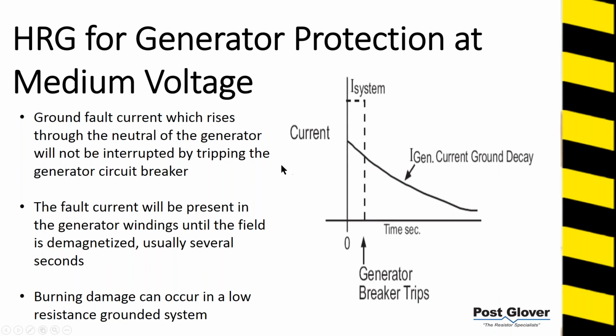And so once again, if you talk about hybrid grounding, that's the situation where you can't use high resistance ground exclusively because of the capacitive charging current, but sometimes you can because the charge current is lower. I know I've said a lot about the charge current. We'll go over more detail in a second. So if you just have a low resistance ground system, just as an FYI, it's possible that you can get additional damage. It has been shown in some IEEE papers for some pulp and paper facilities out west.